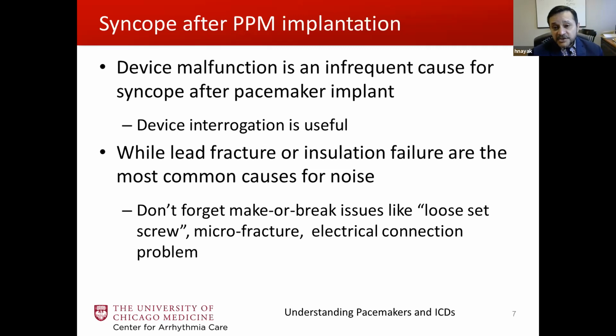So device interrogation is extremely useful. Now, we've seen examples of lead fracture and insulation failure. They're the most common causes of device failure, certainly noise. But don't forget these make or break issues like loose set screw, microfracture, or electrical connection problems. And the interesting part of this case is that it seemed to manifest literally 5 years after his initial implant.